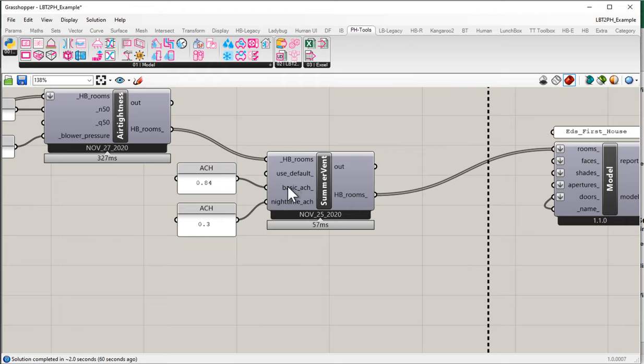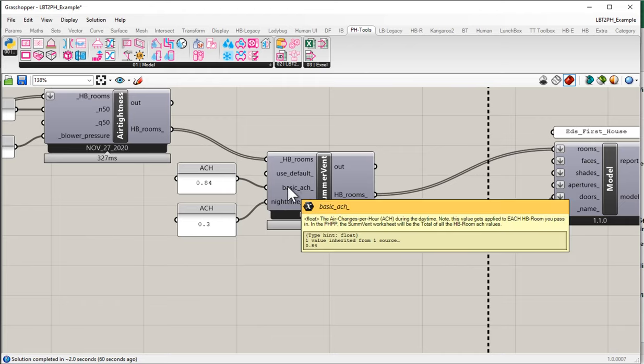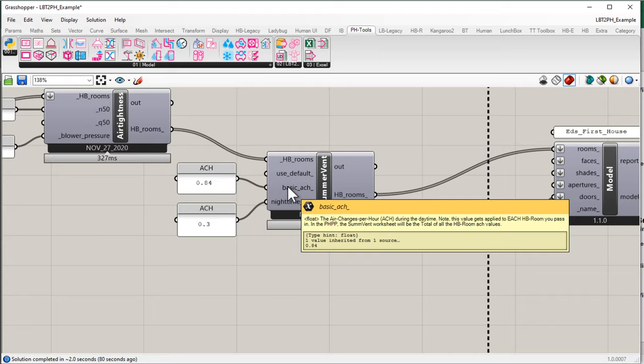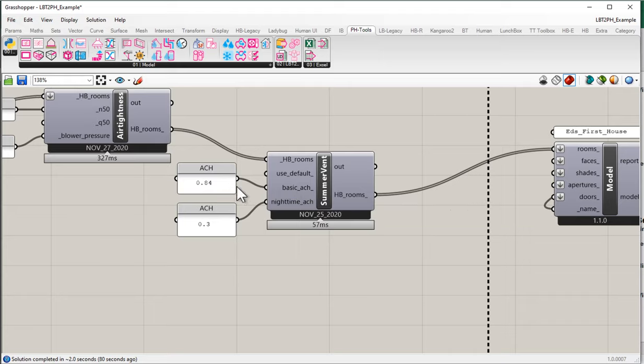Well, if you notice, if you take a look at the tool tip here, it says that the value is an air change rate during the daytime. Note that this value gets applied to each honeybee room that you pass in. In the PHPP, the summer ventilation worksheet will be the total of all of the honeybee room ACHs. The reason it does that is sometimes you might want different airflow for different rooms.